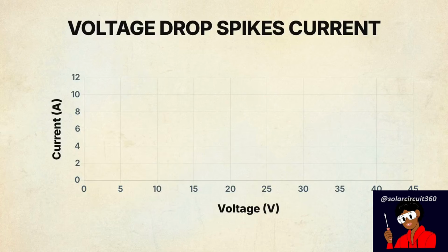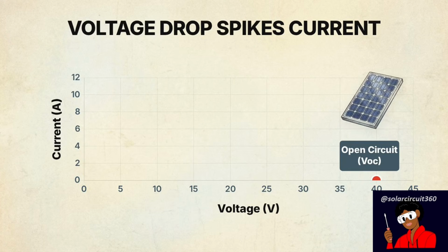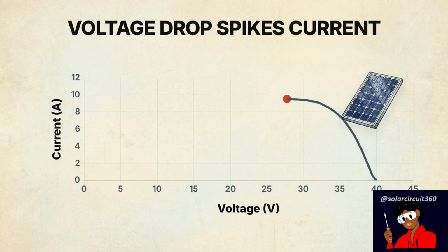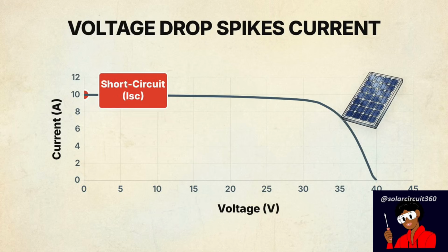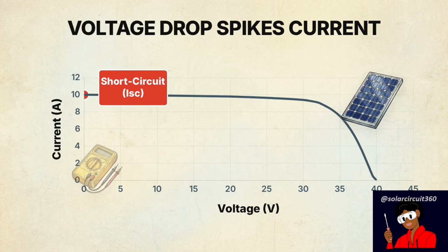This chart is the IV curve. Engineers use this visualization to trace exactly how a panel reacts as resistance drops and the circuit closes. The curve demonstrates that as the measured voltage falls away, the current rapidly rises. The final resting point on the vertical axis, where voltage hits zero, is the short circuit current, or ISC.